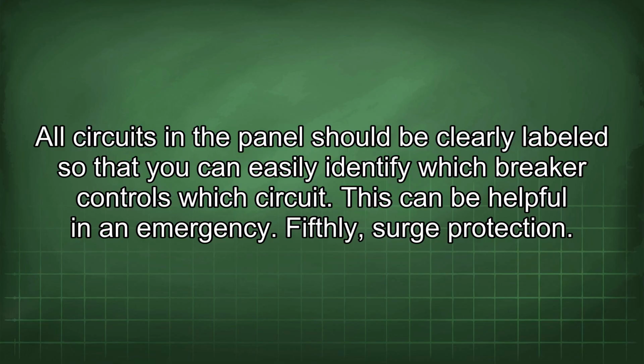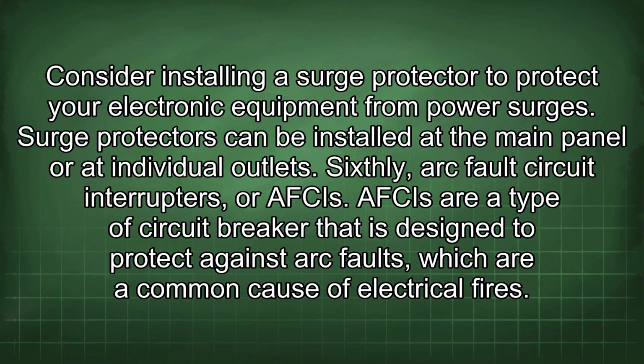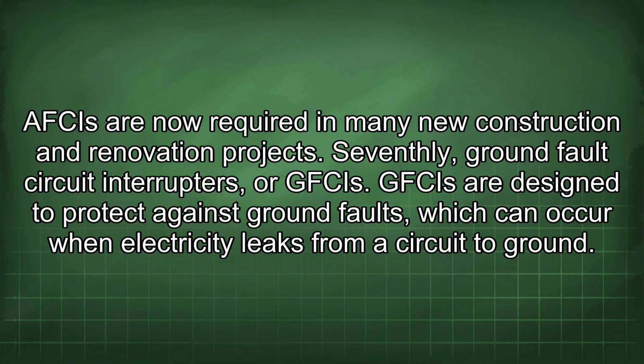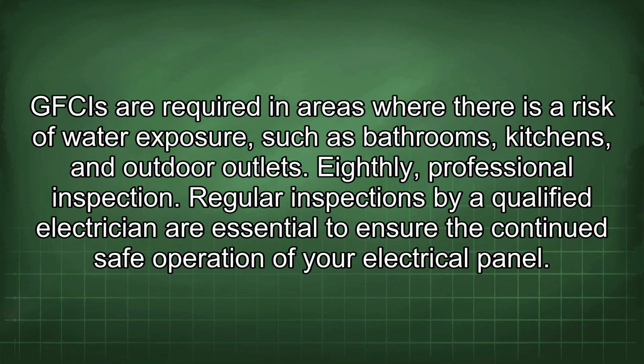Fifthly, surge protection. Consider installing a surge protector to protect your electronic equipment from power surges. Surge protectors can be installed at the main panel or at individual outlets. Sixthly, arc fault circuit interrupters, or AFCIs. AFCIs are a type of circuit breaker that is designed to protect against arc faults, which are a common cause of electrical fires. AFCIs are now required in many new construction and renovation projects. Seventhly, ground fault circuit interrupters, or GFCIs. GFCIs are designed to protect against ground faults, which can occur when electricity leaks from a circuit to ground. GFCIs are required in areas where there is a risk of water exposure, such as bathrooms, kitchens, and outdoor outlets.